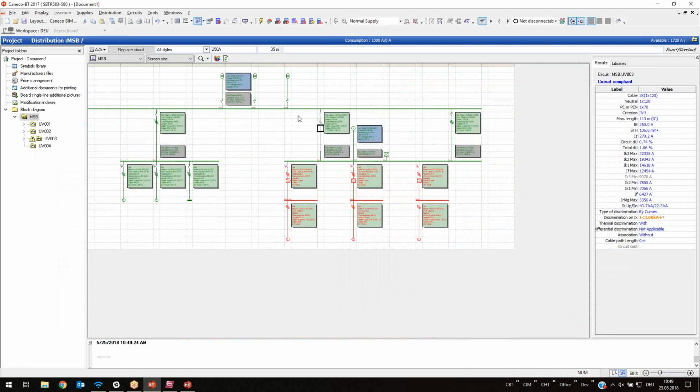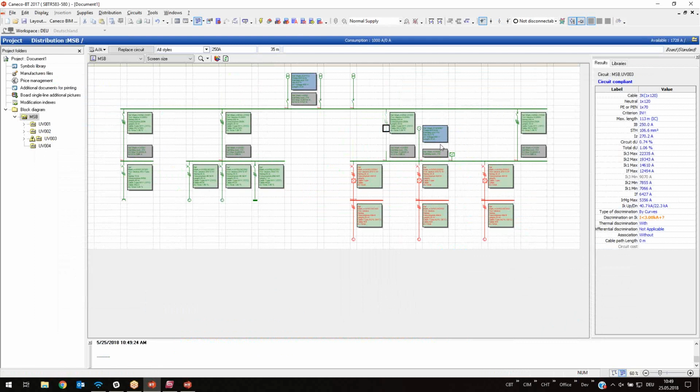Okay, that's it. And now we have a normal supply, emergency supply, and UPS supply. And what happens right now is that the downstream circuits are looking upstream for the biggest short circuit current regarding the maximum breaking capacity of the protection device. So they check if the biggest current is coming from the UPS, from the genset, or from the transfo, of course from the transfo in our case. And the smallest short circuit current regarding the tripping unit will be out of range.